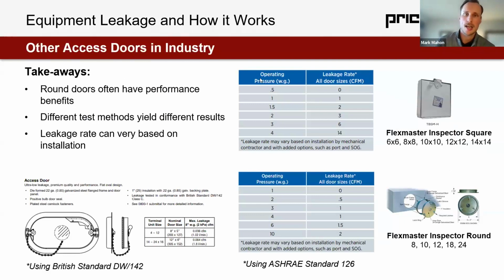I would also argue it's a little bit of a cost add, and that's why we often see screws used instead of latches or quarter turn sash latches. I would say specify a latched door instead of a screw door. If you specify that, then you're going to get an equivalent option from all manufacturers. And I think it is preferable for reinstallation of the door after servicing, or testing and balancing, or cleaning of a coil, or whatever you might be doing maintenance-wise. You're going to have a more repeatable install with a latch rather than a screw. So my recommendation would certainly be to go for a latch instead. Thank you for the question, Heidi.